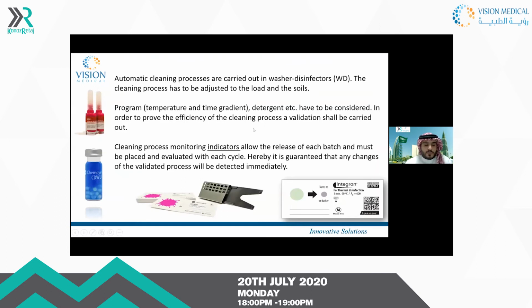Here we will deal with what we do as we work in the CSSD. The main thing in our work is quality. So when we do the disinfection procedure, either manual or automated, we should have some indicators to know how our choice of disinfectant at the beginning is performing. We have different machines in the decontamination area, ultrasonic or washer disinfector, even cart washer. We need to check and have the proper indicators to test. Also, we need to make a manufacturer guideline about the temperature and the time. We also need to consider the cleaning efficiency by doing a validation with the proper disinfectant or chemical.